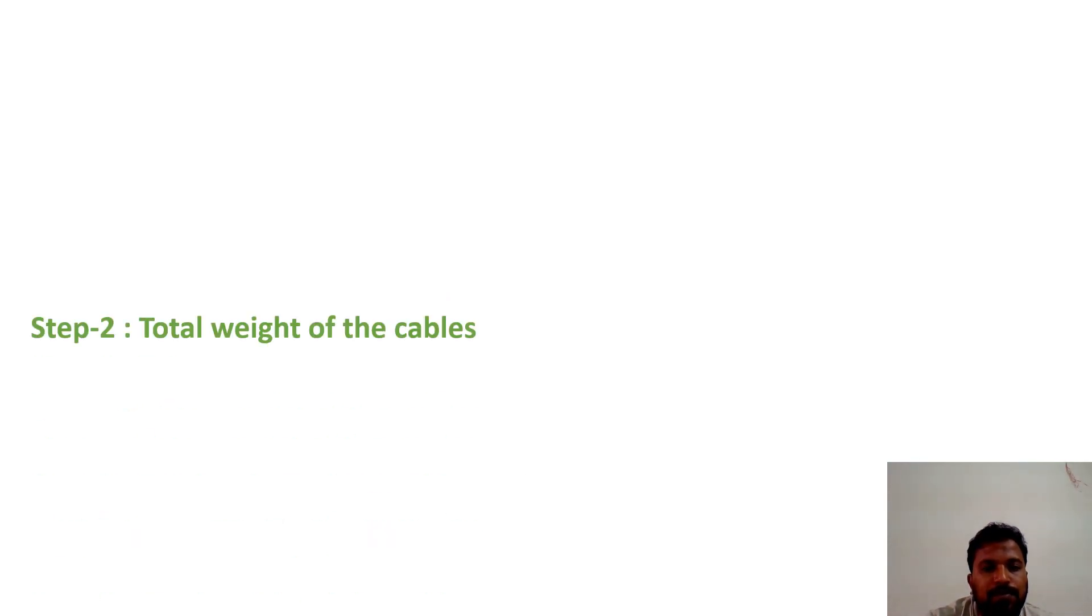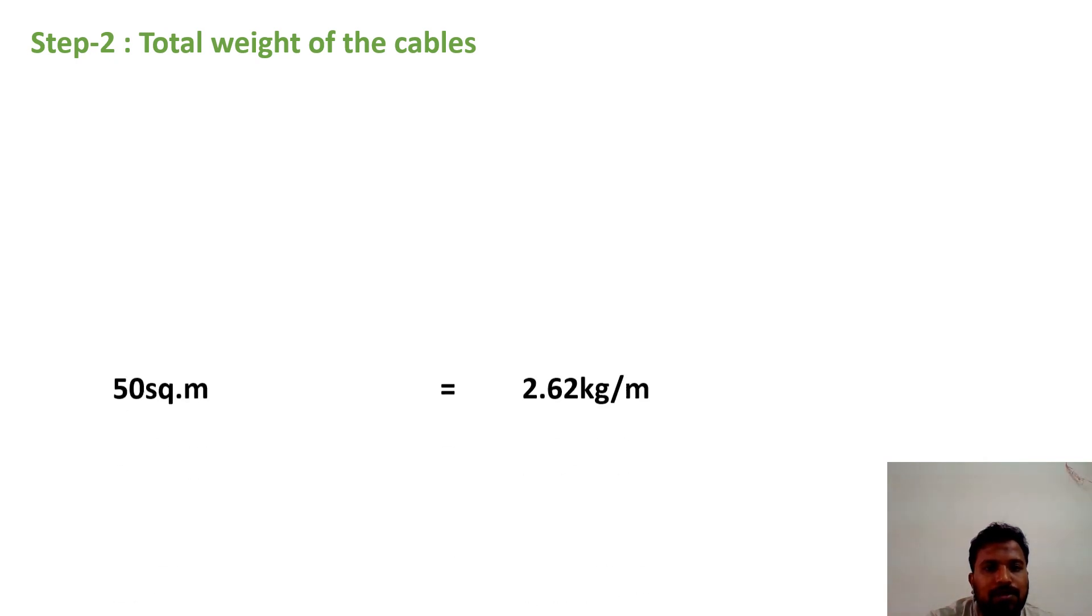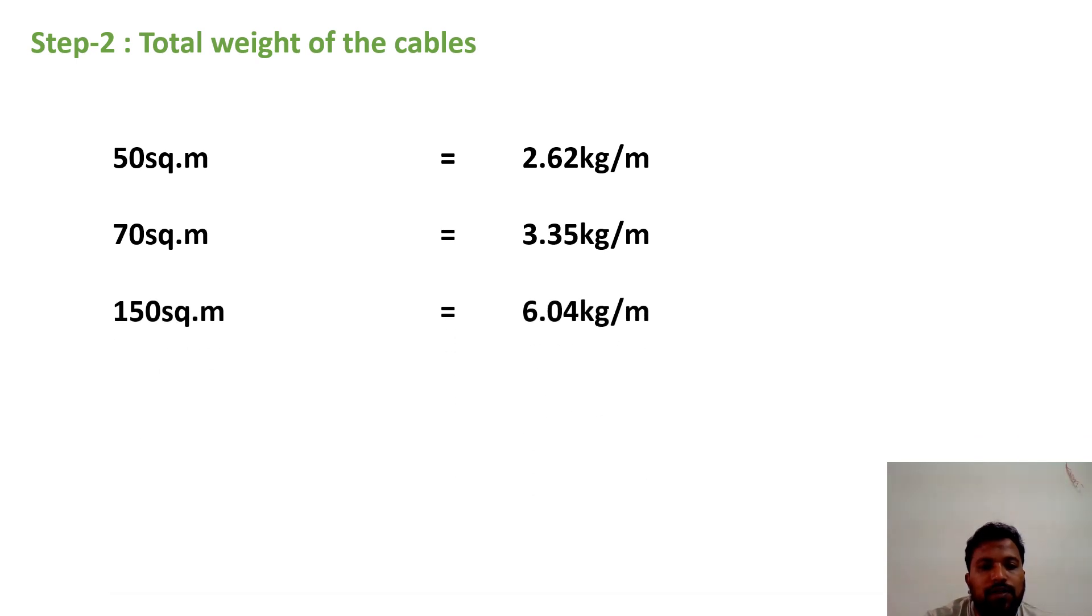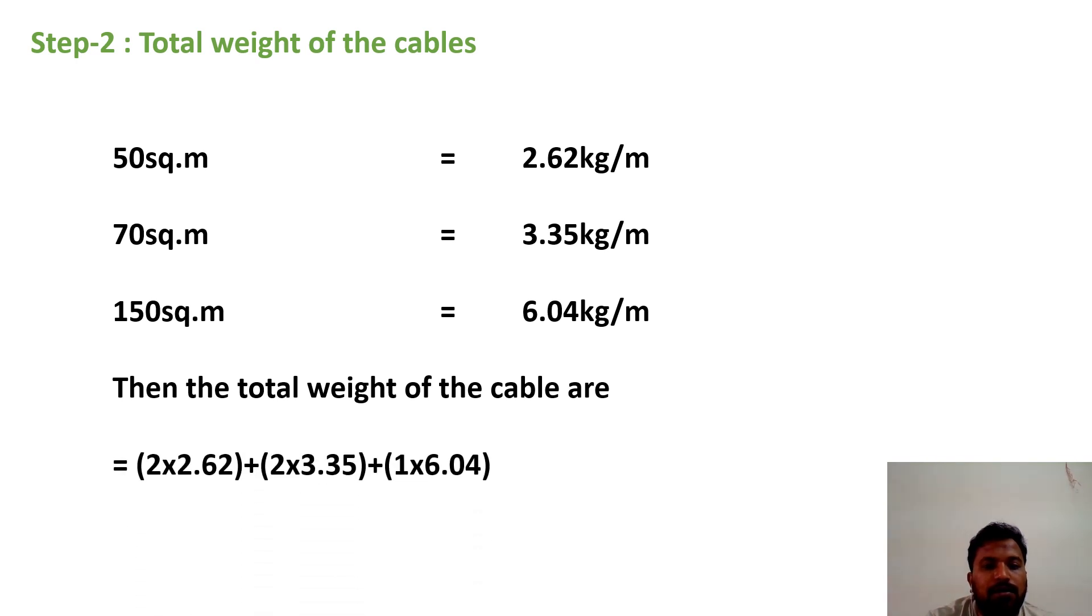Next step, step 2. Total weight of the cables. 50 square mm is 2.62 kg per meter, 70 square mm is 3.35 kg per meter, and 150 square mm is 6.04 kg per meter. Similarly, these values also I got from the cable manufacturing chart. If you add all those weights, 2 into 2.62, 2 into 3.35, 1 into 6.04. If you are adding all those values, 18.8 kg per meter square.